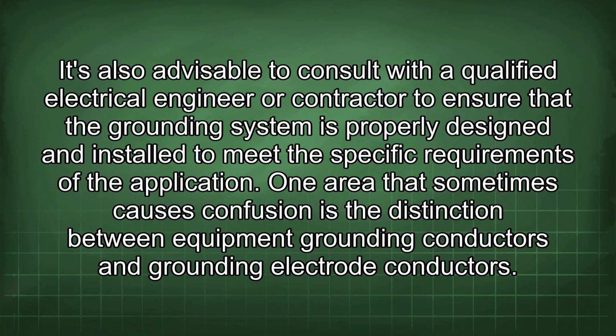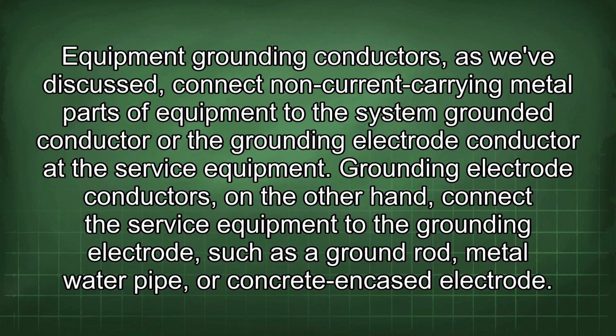One area that sometimes causes confusion is the distinction between equipment grounding conductors and grounding electrode conductors. Equipment grounding conductors, as we've discussed, connect non-current carrying metal parts of equipment to the system grounded conductor or the grounding electrode conductor at the service equipment. Grounding electrode conductors, on the other hand, connect the service equipment to the grounding electrode, such as a ground rod, metal water pipe, or concrete encased electrode.